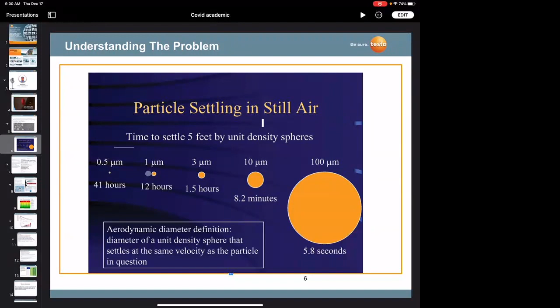But you see there's a great big jump when you go from 12 to 13. An amazing jump by a factor of threefold in its ability to capture. And that's the whole game here, is what can we do in the best possible practices to achieve these numbers. And so that's why MERV 13 is mentioned. And a MERV 13 filter does not cost that much more than a MERV 4 filter. This is a study that was done back in 2013. I went online to check prices, and they're still about the same range, but there's maybe a $20, $30, $40 price difference between a MERV 13 and a MERV 4.